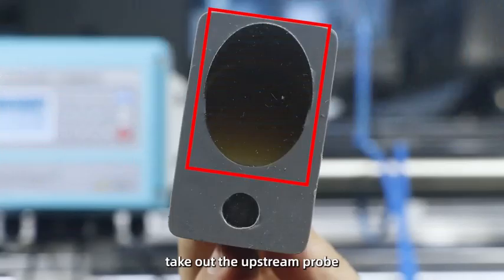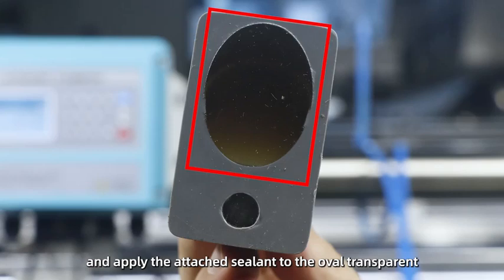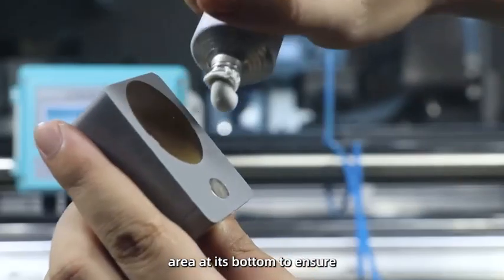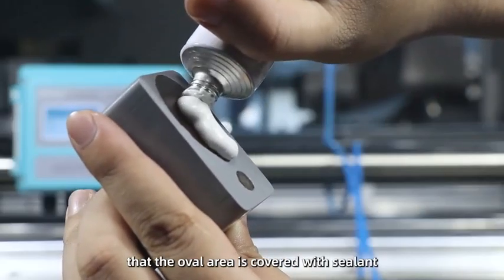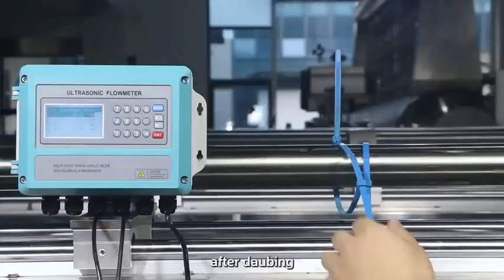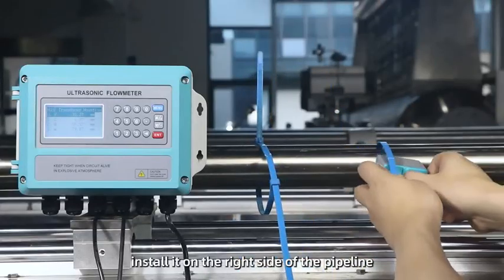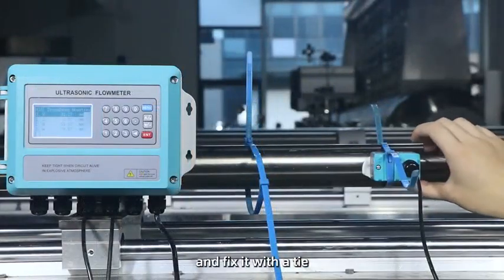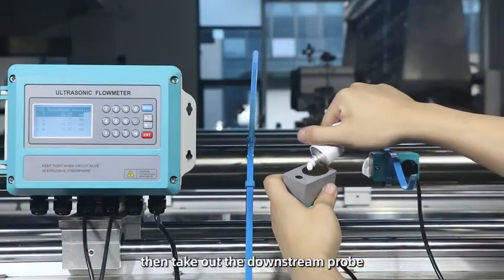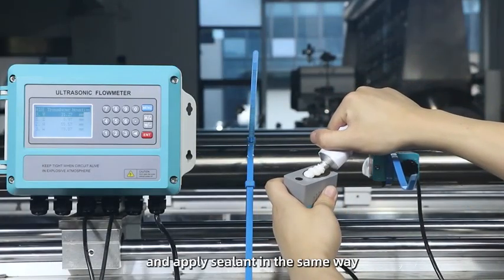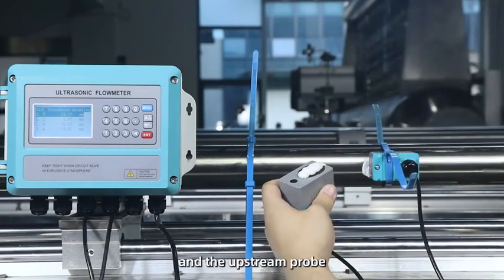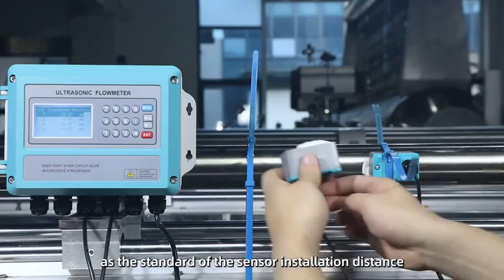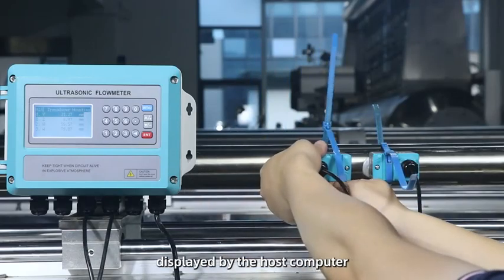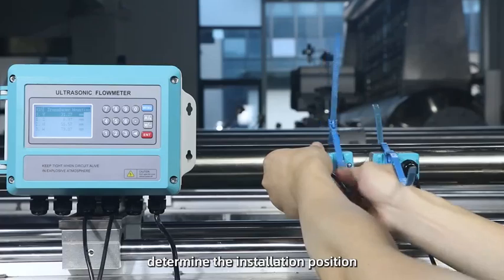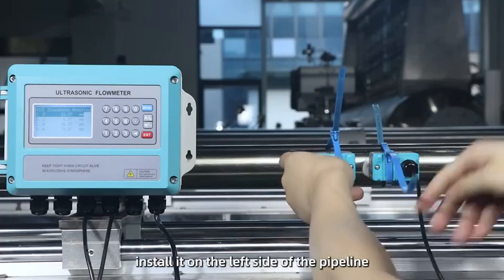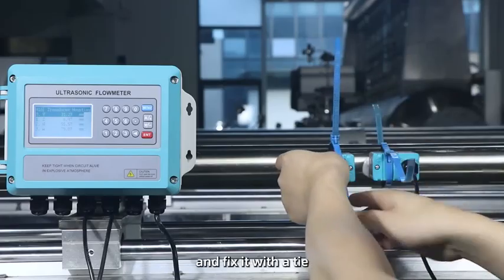Take out the upstream probe and apply the attached sealant to the oval transparent area at its bottom to ensure that the oval area is covered with sealant. After daubing, install it on the right side of the pipeline and fix it with a tie. Then take out the downstream probe and apply sealant in the same way. Take the distance between it and the upstream probe as the standard of the sensor installation distance displayed by the host computer. Determine the installation position. Install it on the left side of the pipeline and fix it with a tie.